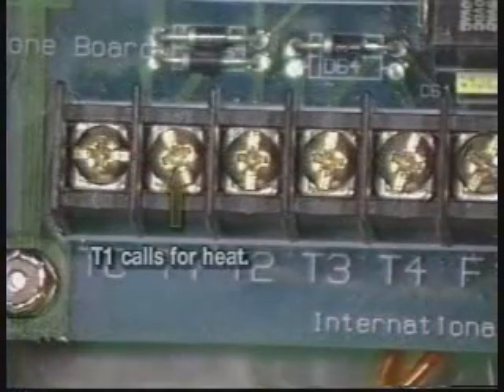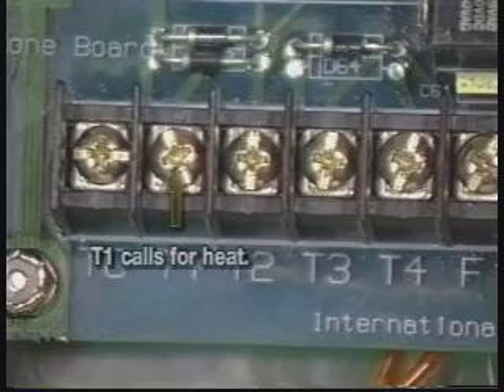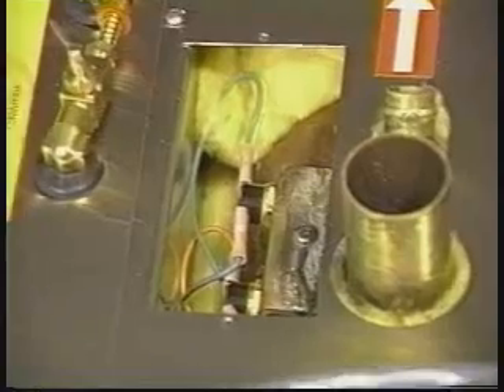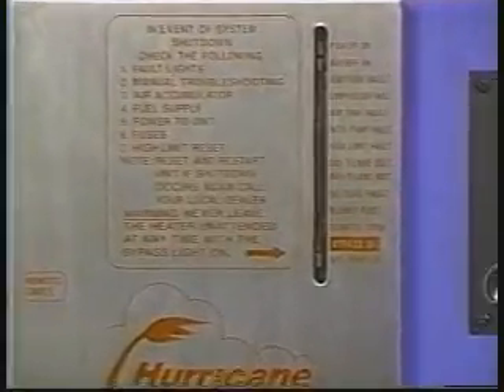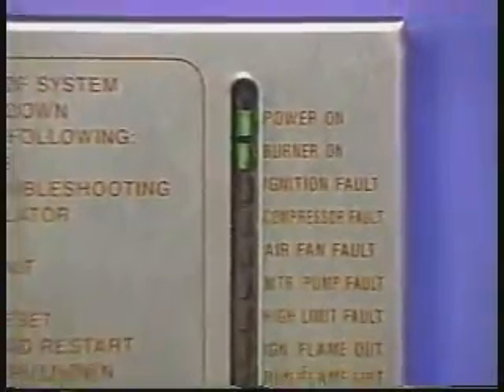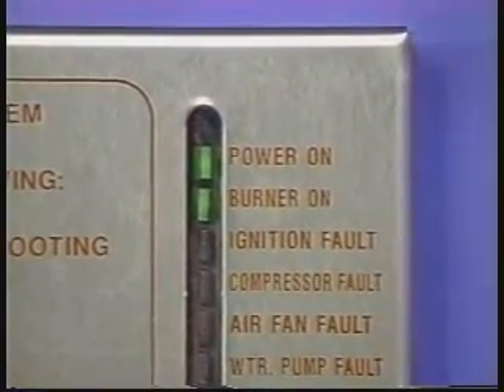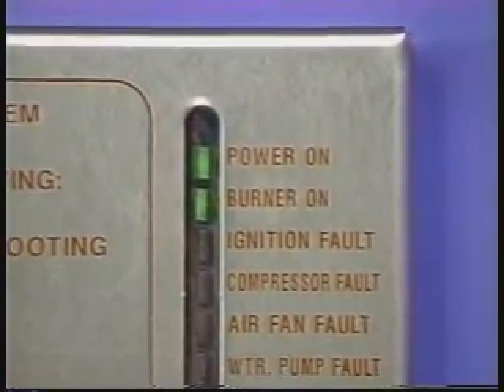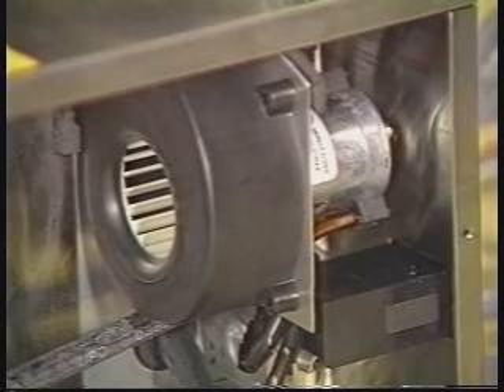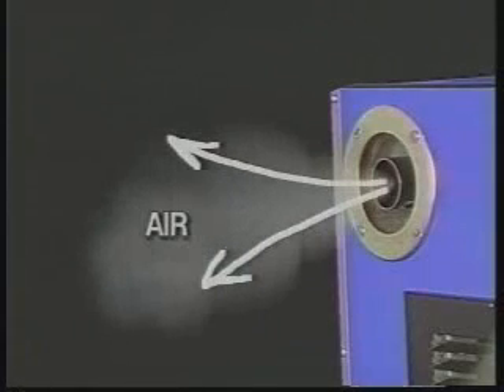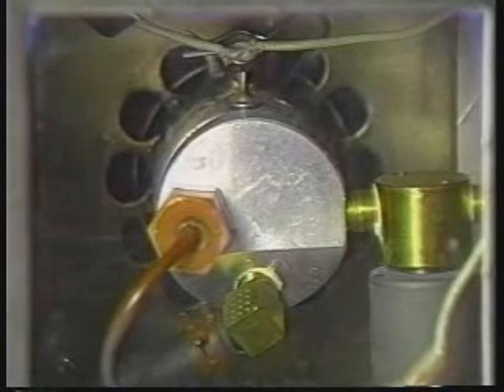Let's assume that T1, or thermostat 1, has called for heat and that the operating or cycling aquastat is closed. The power on green light at the top of the board is on, and then the thermostat circuit closes. The second green light, burner on, lights. The combustion air fan begins to run, and air will come out of the exhaust. Immediately after the air fan starts, the igniter pin begins to glow.